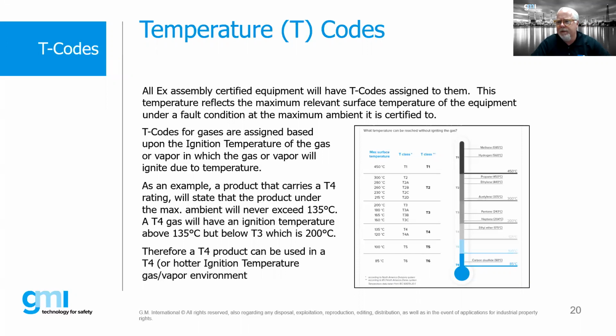There's some examples of ignition temperatures, and this is where we use the ignition temperature of the gas as our determination for our T code. So you can see on there things like methane is very, very high. Hydrogen is about 560 degrees C. Propane's 450 degrees C. Those are the temperatures at which propane or some of those other gases will spontaneously ignite when exposed to those temperatures, as opposed to having some sort of arc or spark or something that is a catalyst that starts that explosion.